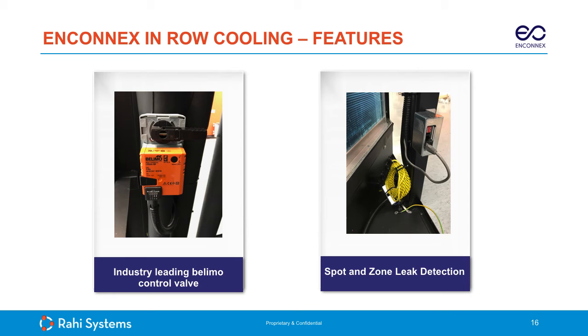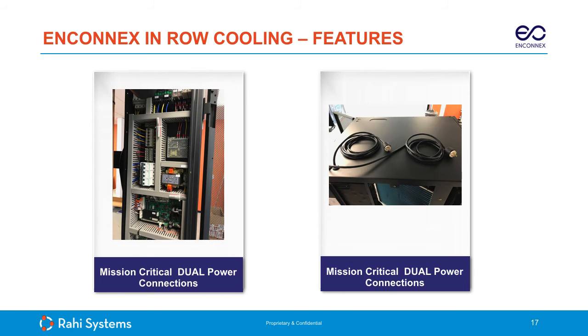So yeah, the Belimo valve, that's the control valve on the chill water unit. Very reliable, very available, at many different entering water temperatures. Also selected for the fact that it is easy to source and replace in the United States and Europe and Asia. That was key for the supportability of the system. There's actually a spot and a rope leak sensor, and it's standardly provided with all the units, which is also key for any potential leaks. And then on the next slide we show the power configuration. It's actually a dual power with a built-in auto transfer switch, and that's standard on all the systems for electrical redundancy.